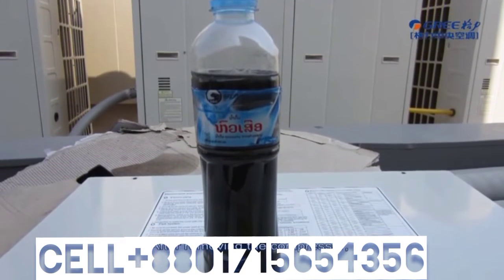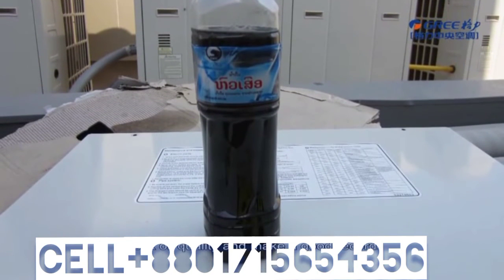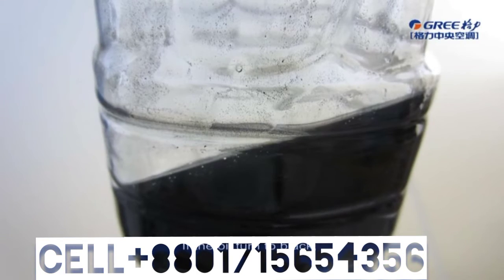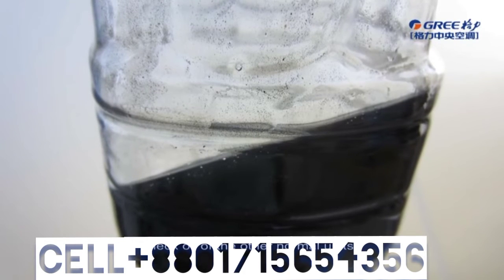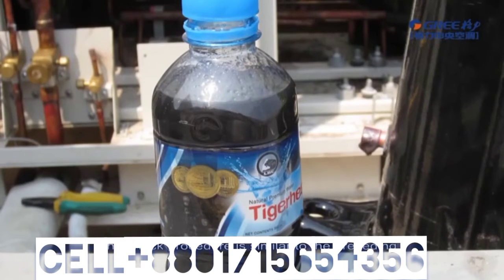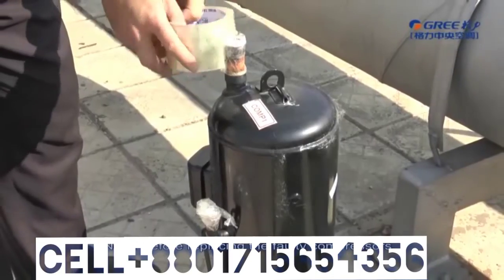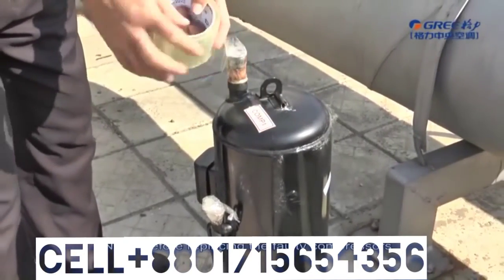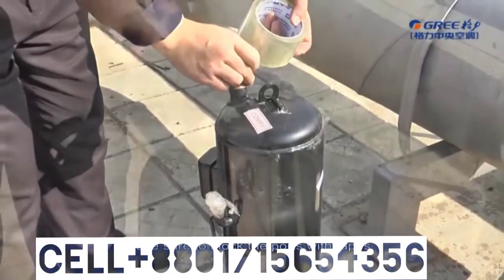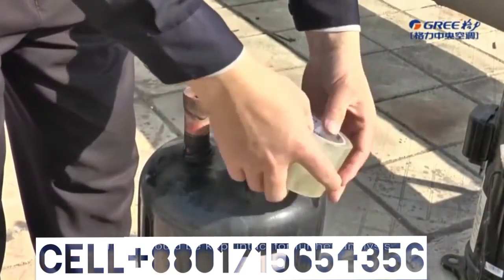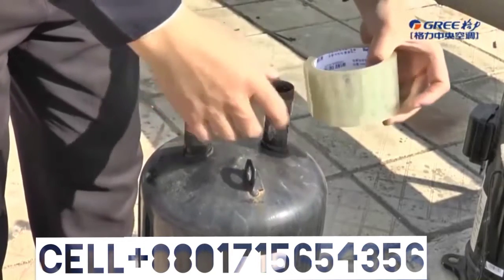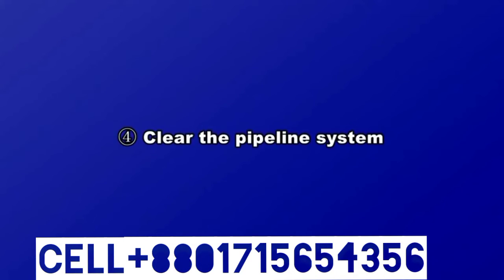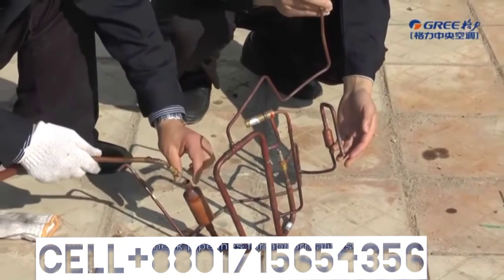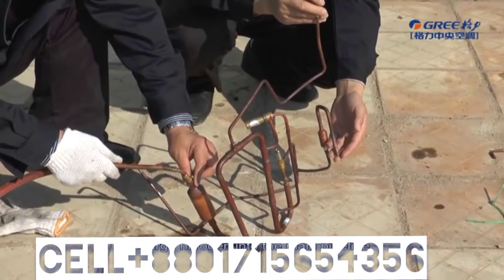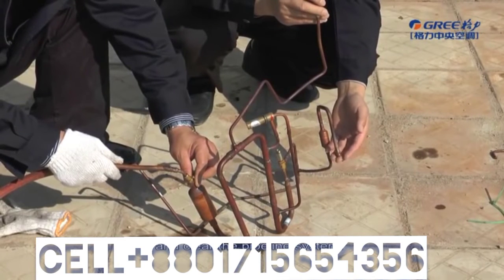After removing the compressor, check oil quality and make a good record. If the oil turned black, check oil of the other normal units. The check procedure is similar to the preceding. Note: before replacing the faulty compressors, make sure to block the ports with tapes. They should be kept intact for further analysis. Step 4. Clear the pipeline system. Check pipelines for abnormalities. Charge nitrogen into the main pipeline and clear the pipeline system.